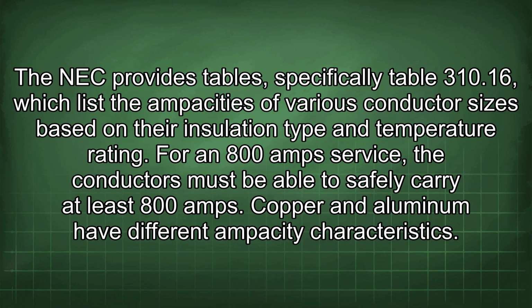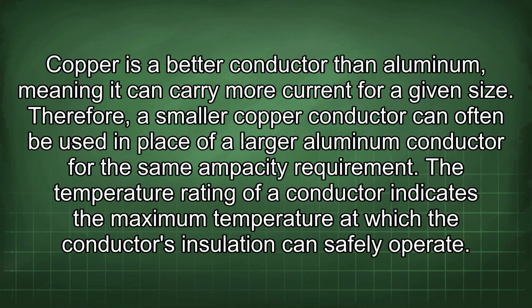The NEC provides tables, specifically Table 310.16, which lists the ampacities of various conductor sizes based on their insulation type and temperature rating. For an 800 amp service, the conductors must be able to safely carry at least 800 amps. Copper and aluminum have different ampacity characteristics. Copper is a better conductor than aluminum, meaning it can carry more current for a given size.